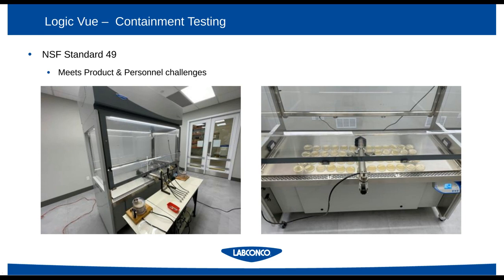To make sure that these enclosures perform, there's a lot of work that goes into performance challenging, and that's done in a biosafety cabinet by way of a biological challenge. The methodologies used for biological challenge assessments are largely dictated by NSF Standard 49 and involve the administration of biological spores across the work surface into the cabinet and then also out of the cabinet. So these are just a couple of representative images. Labconco performs these tests here in addition to NSF as well for other types of enclosures, and regularly evaluates the performance of the products to ensure that they're containing under difficult practices and principles and settings that users may be using the enclosures in.